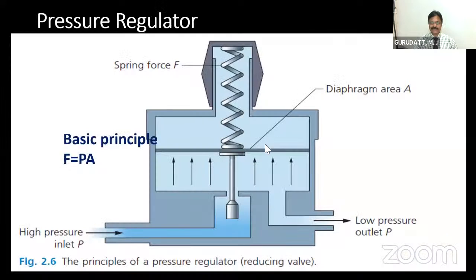Now the other common question you'll be asked is, what is the principle on which these pressure regulators are constructed? How do they operate, how do they reduce the pressure from high pressure to a very low pressure? This is based on a basic principle: force is equal to pressure into area. If we keep the force constant and we increase the area, automatically the pressure has to drop. This is the basic principle under which pressure regulators are constructed.